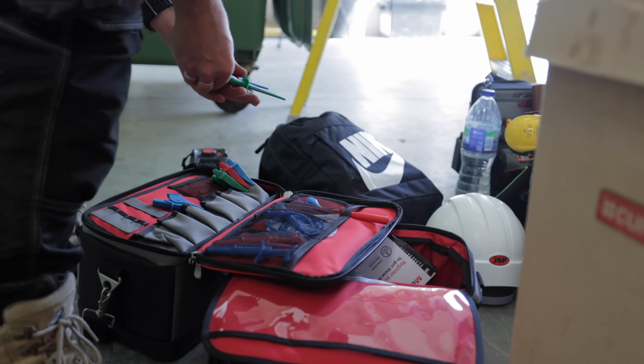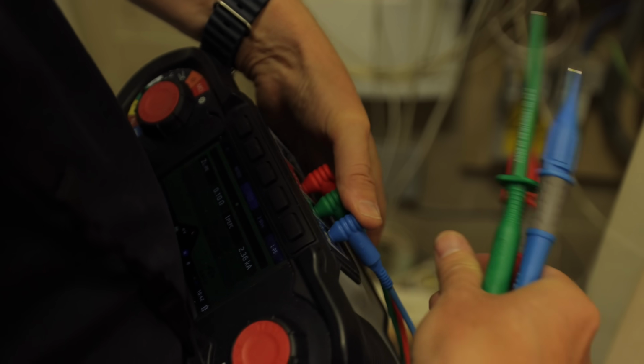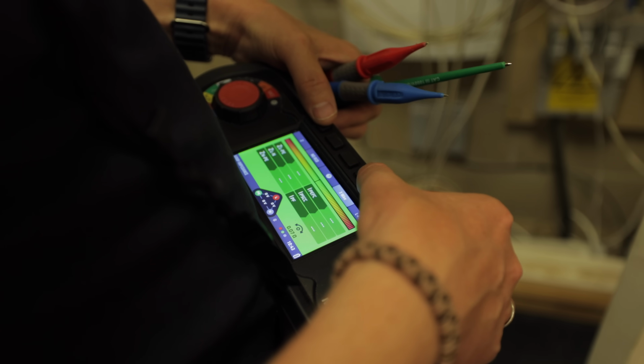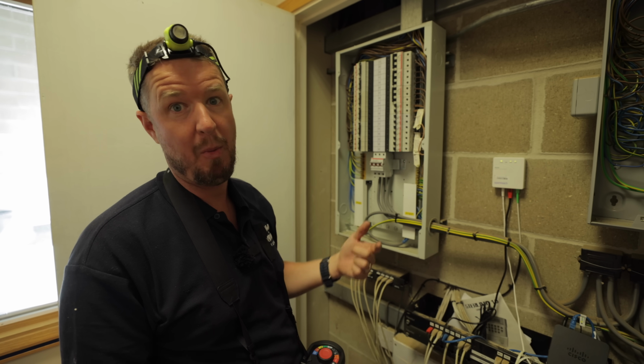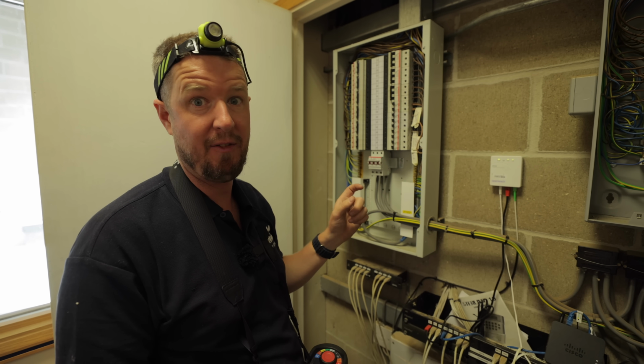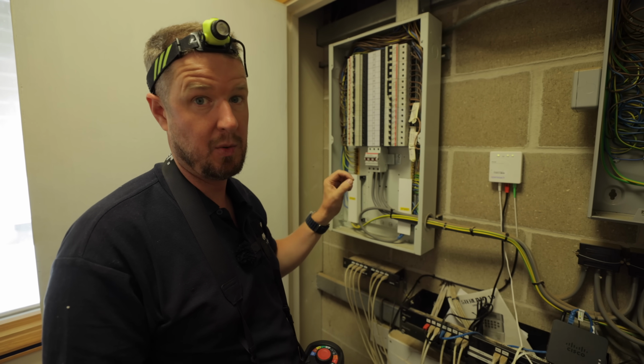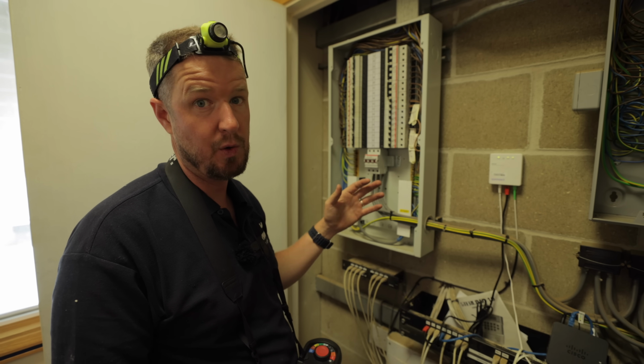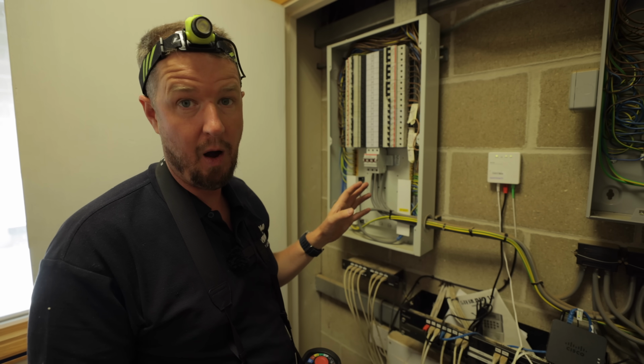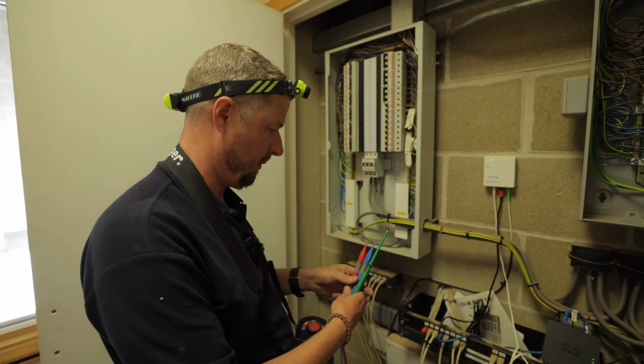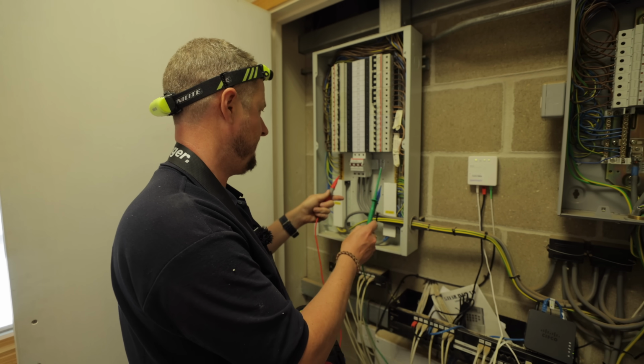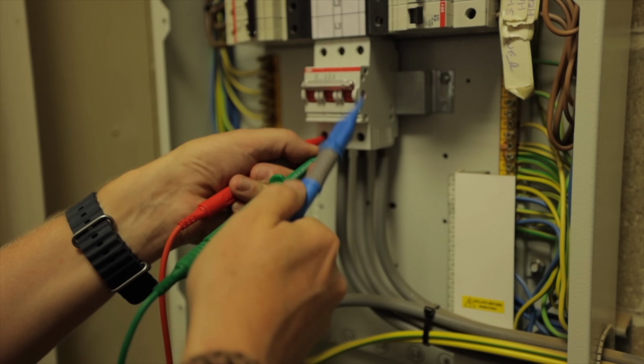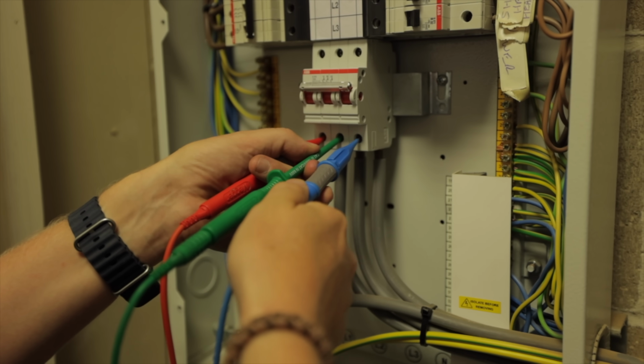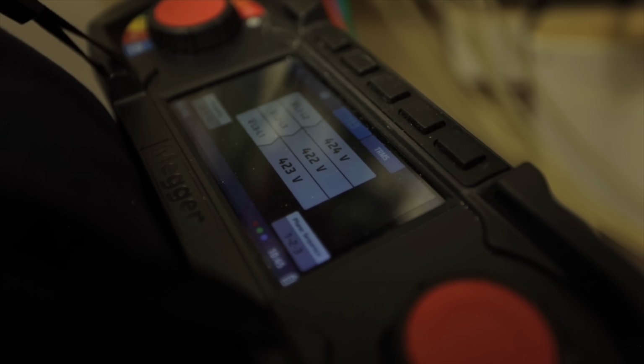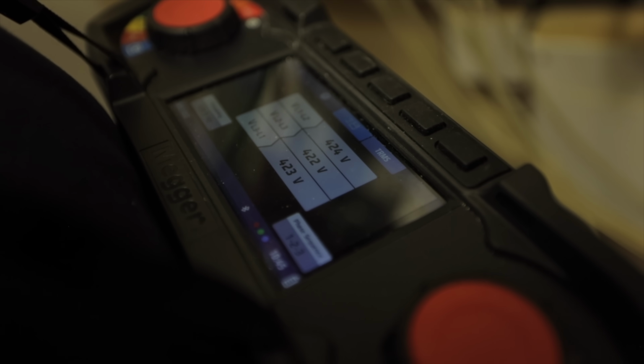Now the next thing we're going to test is our PSC, or prospective short circuit current, which is basically the maximum amount of current that can flow in the event of a direct short circuit between phases or between phases and neutral. We're going to test our phase rotation at this point as well, so I'm going to use all 3 leads here: L1 is red, L2 green, L3 blue. Then on here we've got our voltage, our frequency, and we've also got phase sequence.